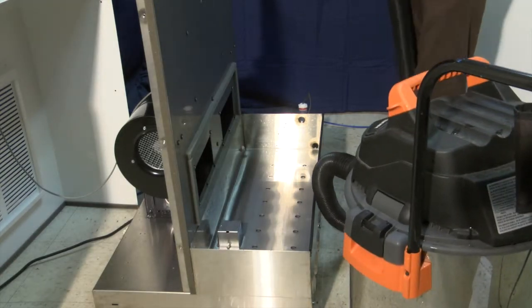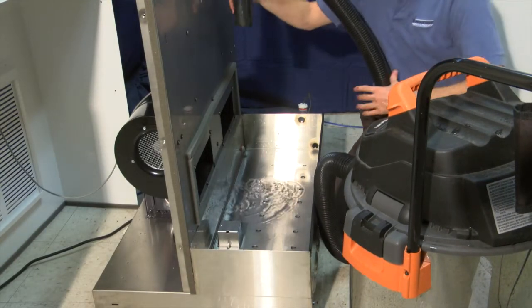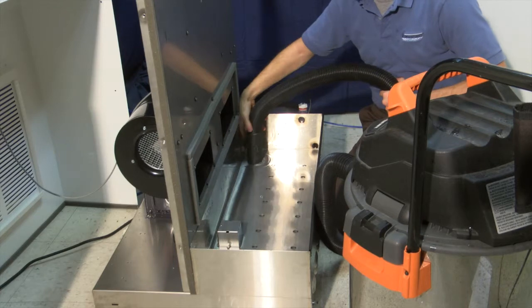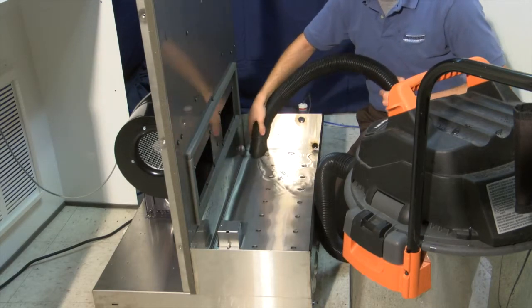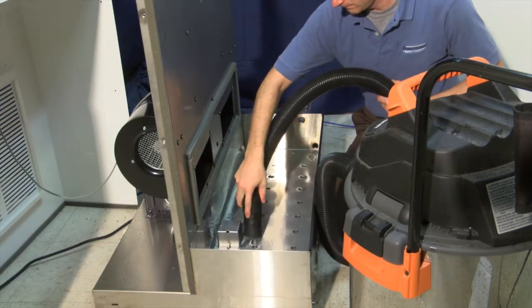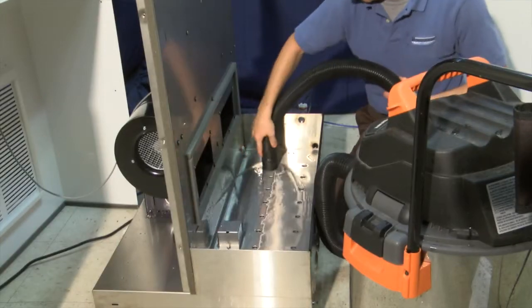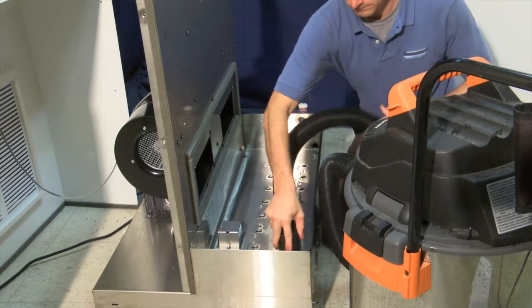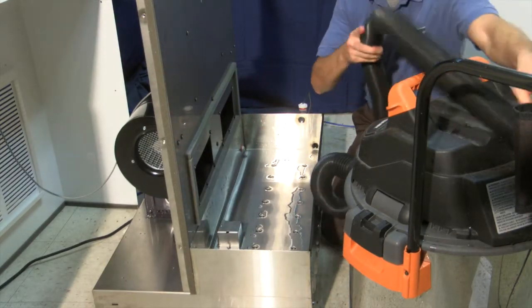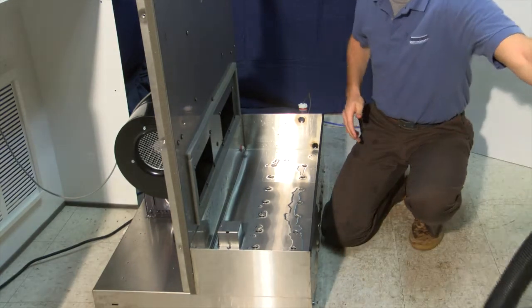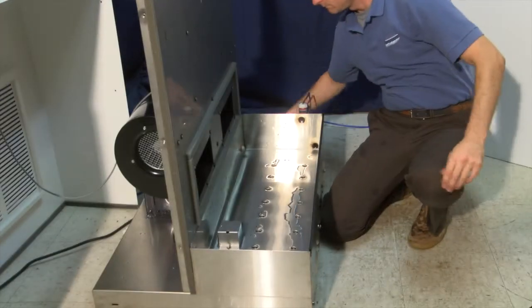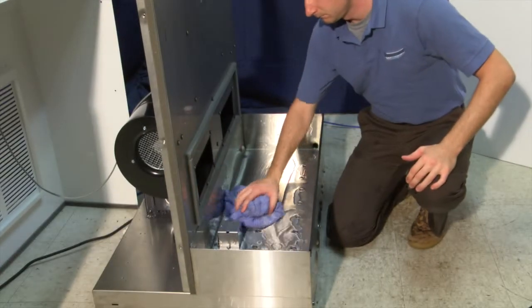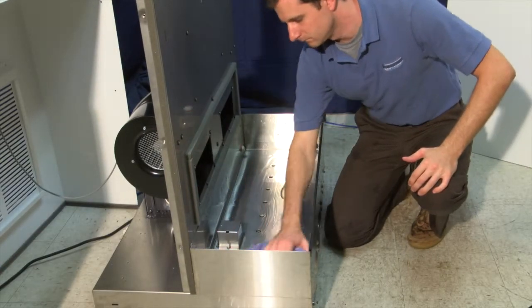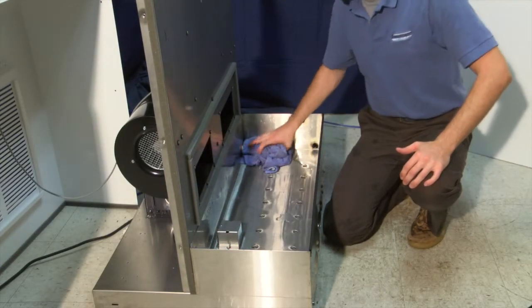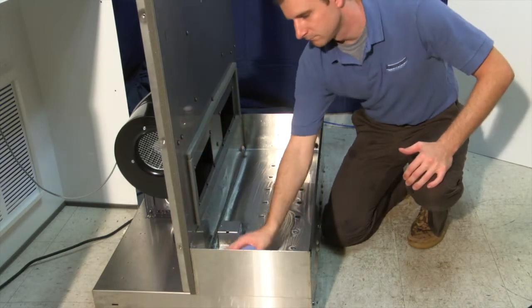Some applications may find they need to clean the inside of the unit to keep the water pan clean and clear. To do this, simply shop vac the water out of the water pan. Use a diluted alcohol or bleach solution and wipe the inside of the water pan out. Do not use a chemical cleaner, as the finishing agents and chemical cleaners can harm the crystallized transducers. You simply want to disinfect the water pan.